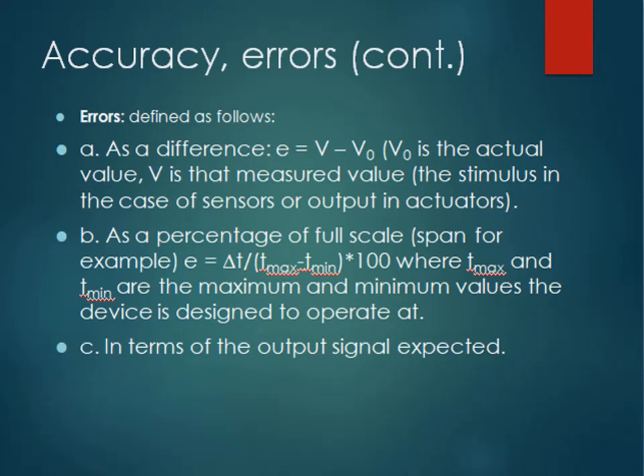As the percentage of full scale, that is span, for example, E is equal to delta T by (T max minus T min) into 100, where T max and T min are the maximum and minimum values the device is designed to operate in. So in terms of the output signal expected.